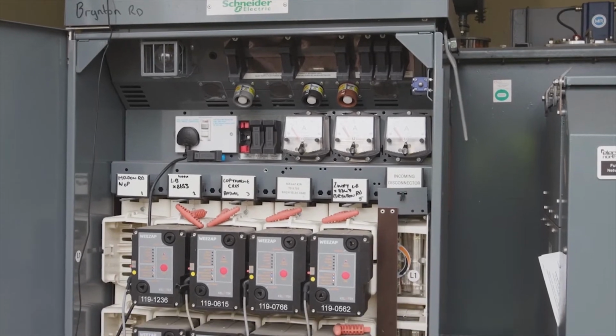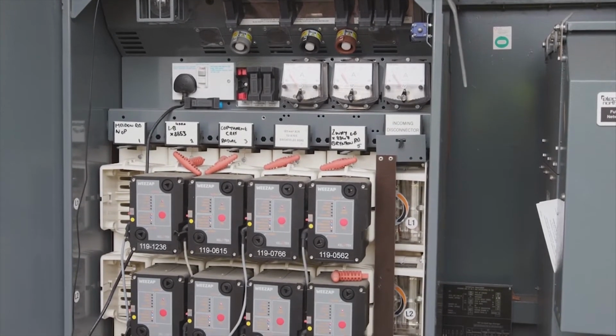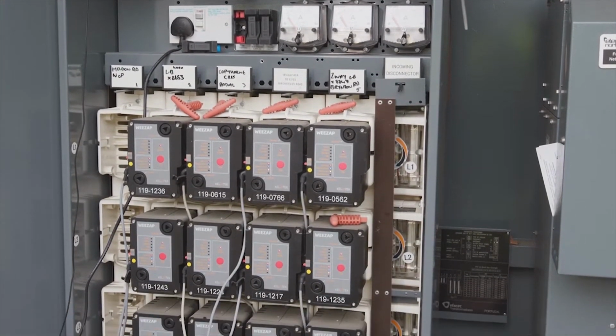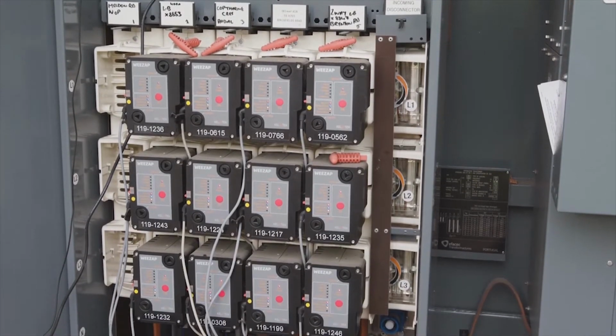We are also meshing the LV network together. At up to 720 LV ways, we'll be replacing the standard fuse with an LV circuit breaker. Those circuit breakers can be remotely controlled and provide measurement data from the substation, such as voltage and amps on the LV way. We'll also be installing LV switches in remote link boxes that will be able to mesh these LV ways together.